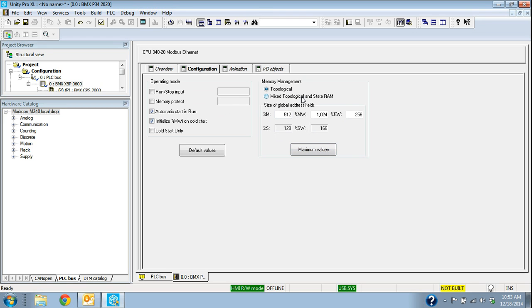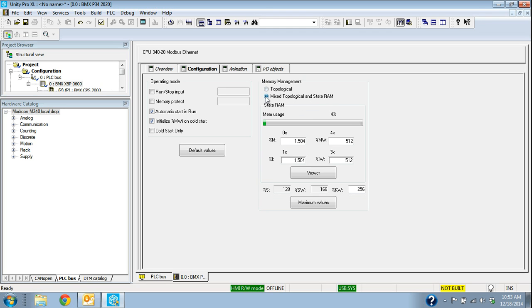Topological and mixed, topological or state RAM addressing, what that is, if I was converting an old, say we're converting an old Compact program, which was an old 984 program, we can import those into Unity. And when we are converting it, the old addresses we refer to as 0x, 1x, 3x, and 4x addresses.